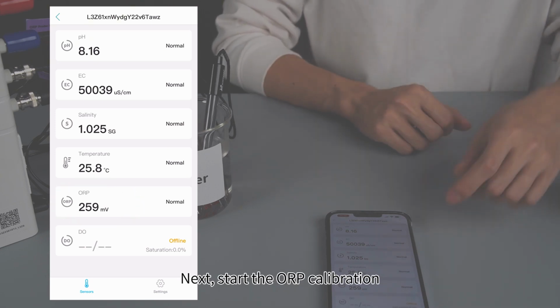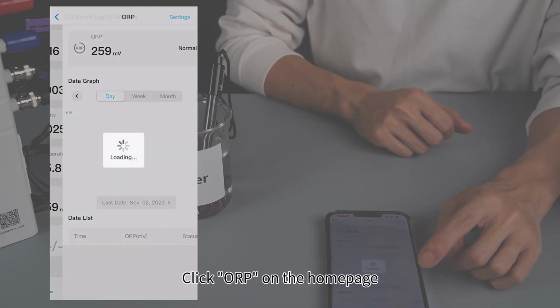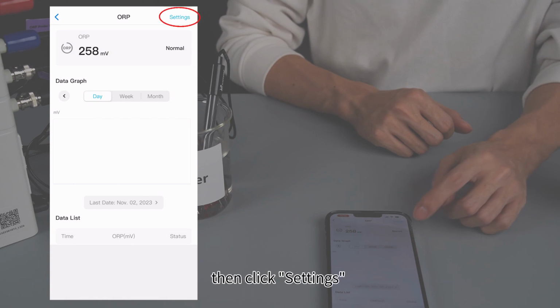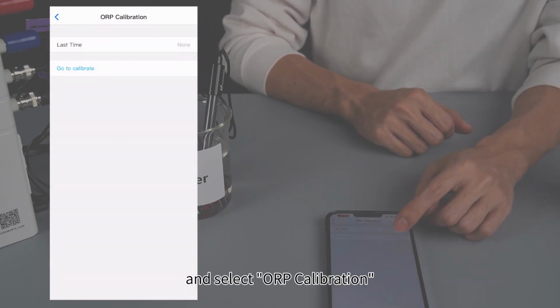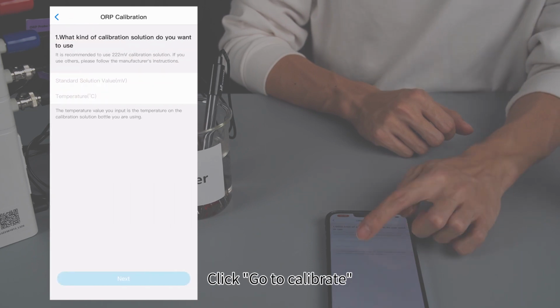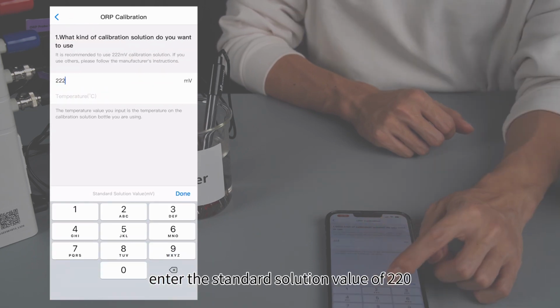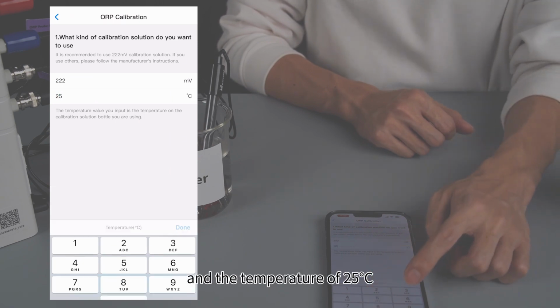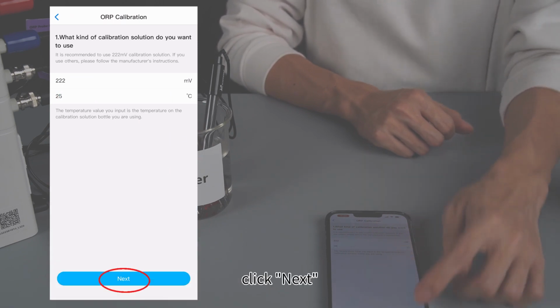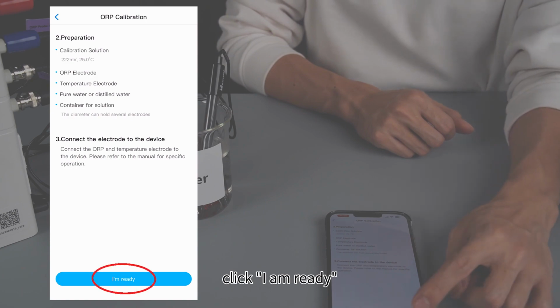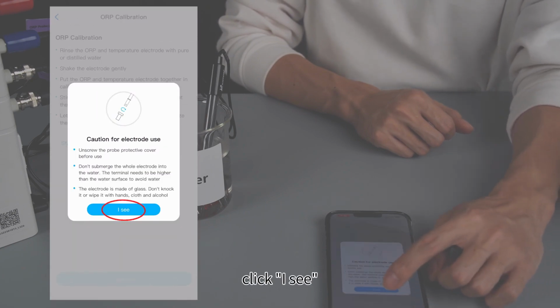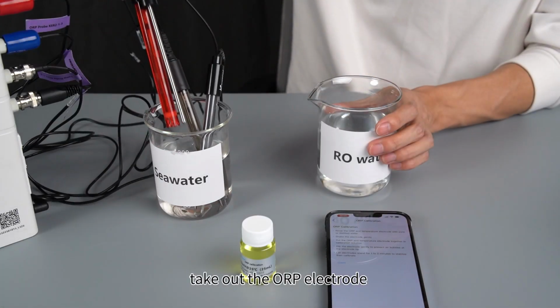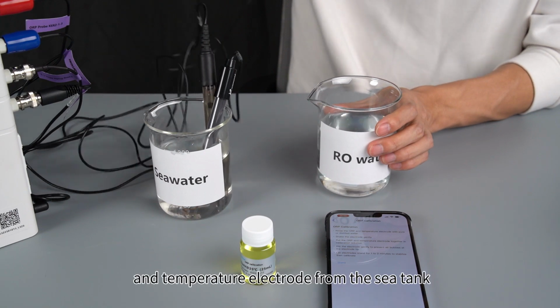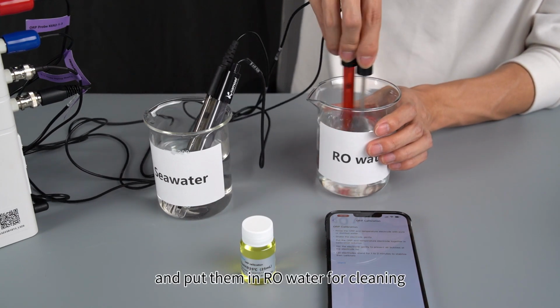Start the ORP calibration. Click ORP on the home page. Then click Settings and select ORP calibration. Click Go to calibrate. Enter the standard solution value of 222 and the temperature of 25 degrees Celsius. Click Next. Click I am ready. Click I see. Take out the ORP electrode and temperature electrode from the sea tank and put them in RO water for cleaning.